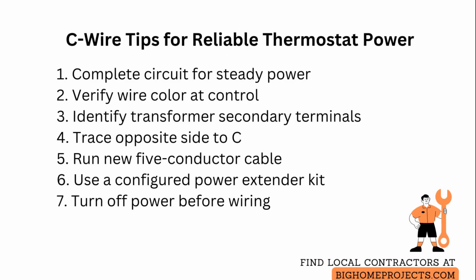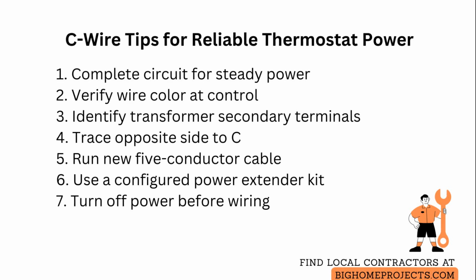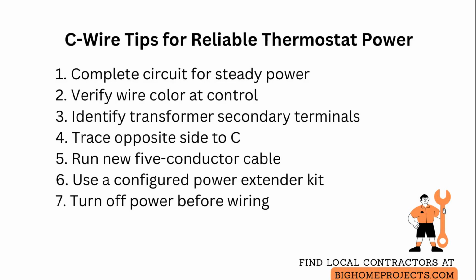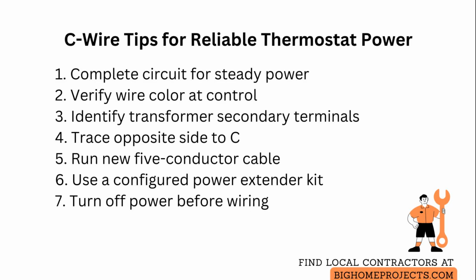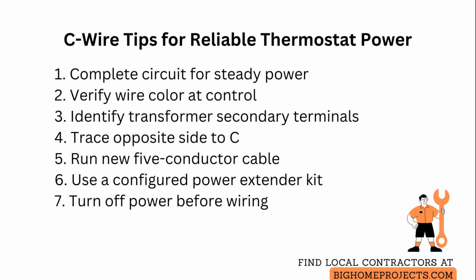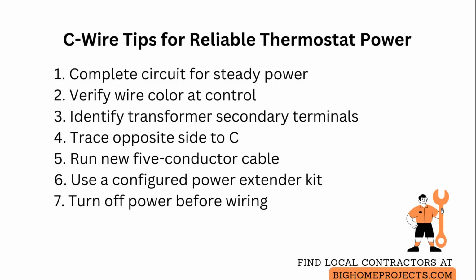On a typical 5-wire thermostat cable, the common conductor is commonly blue, but wire color is not guaranteed, so always verify at the air handler or furnace control board before connecting. If you open the control panel, locate the transformer secondary terminals. Identify the side tied to your R or hot feed, and the opposite side that is available to land on C at both the control board and the thermostat.